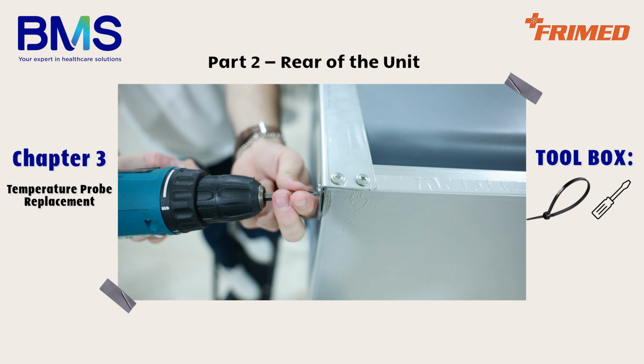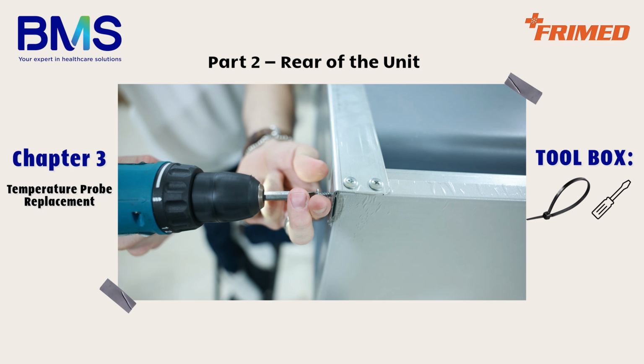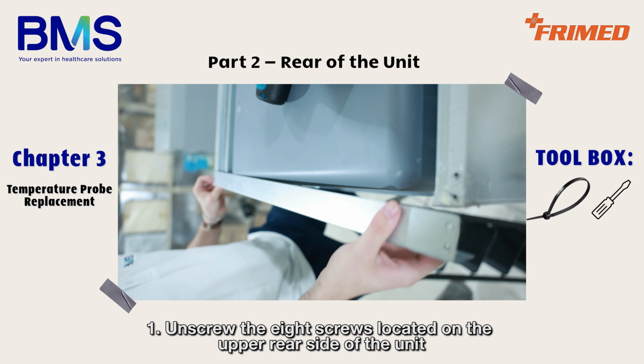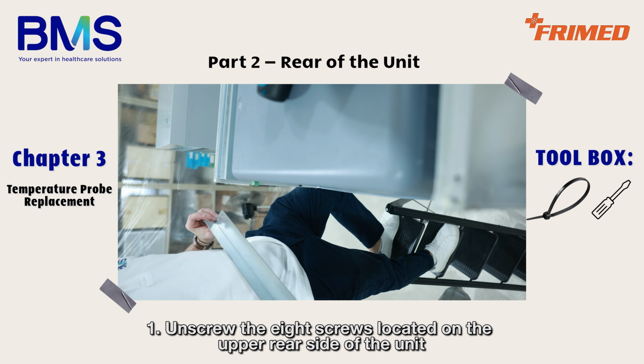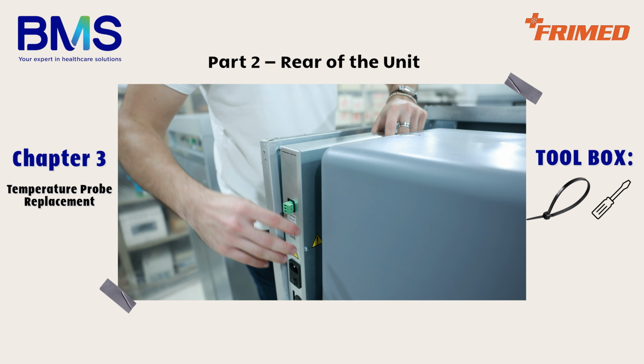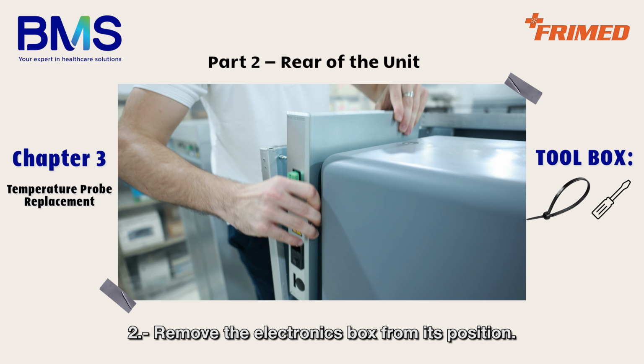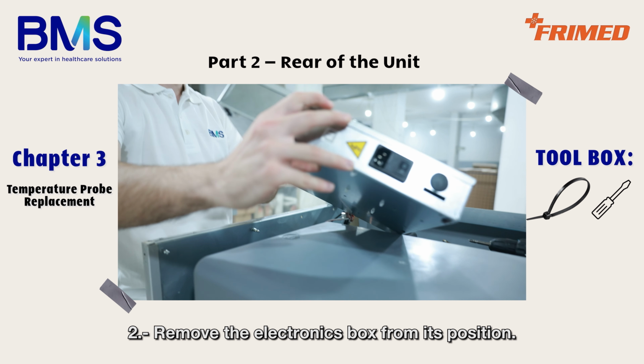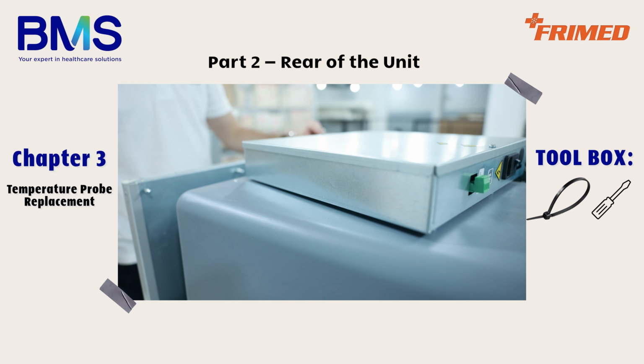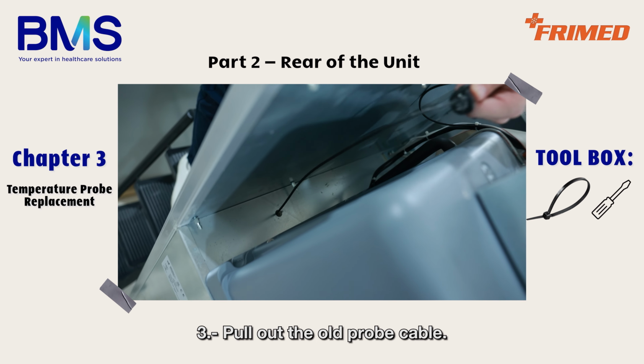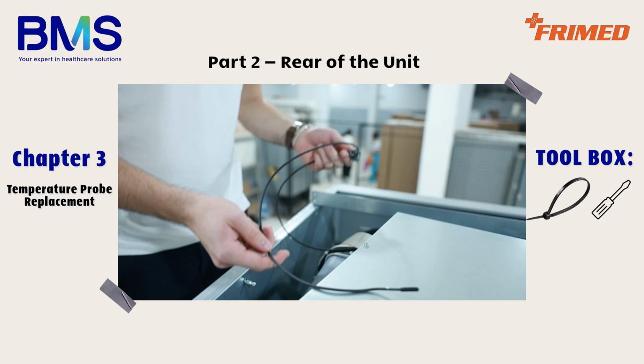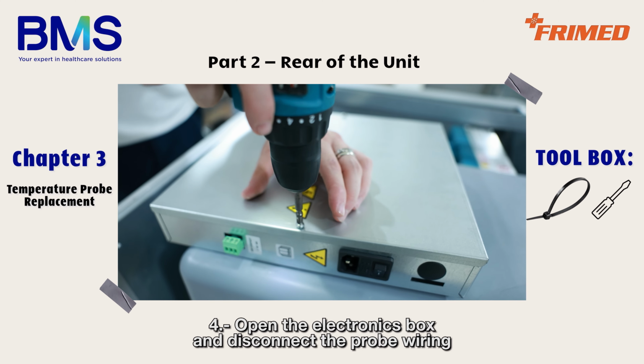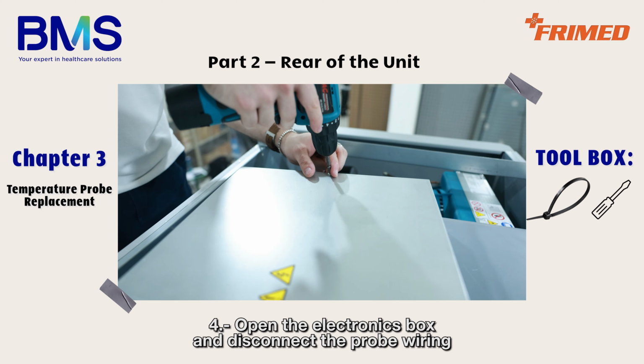Part 2. Rear of the unit. Unscrew the 8 screws located on the upper rear side of the unit and remove the stainless steel bar to access the electronics box. Remove the electronics box from its position. Pull out the old probe cable. Open the electronics box and disconnect the probe wiring from the control board.